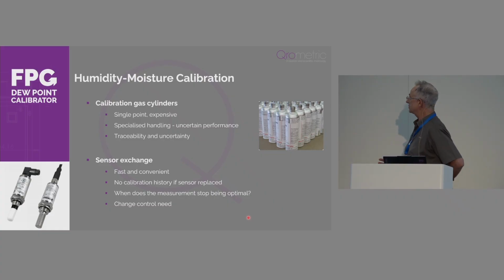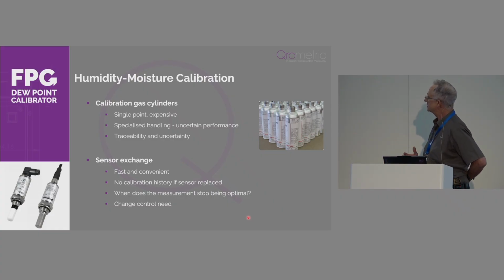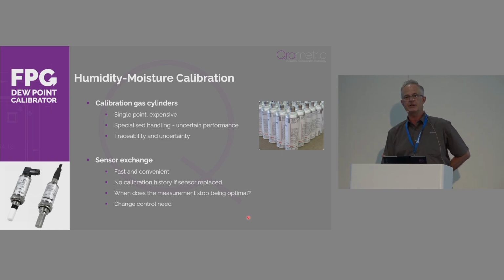Well, the typical systems for humidity and moisture calibration are explained here. So you can use a calibration gas cylinder. So you buy a cylinder of a pre-mixed gas mixture, which you then apply to the analyzer. But these can be very expensive, difficult to handle, quite complex. You have to take them on site. But it's one way of doing it.